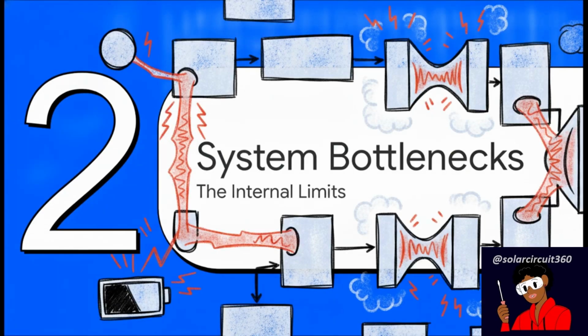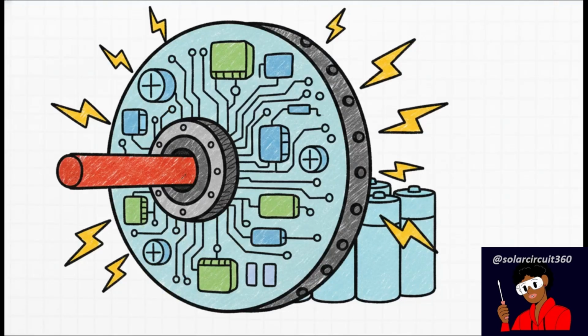Which brings us to system bottlenecks and those strict internal limits. You see, even if your lithium cells are fully charged and ready to go, the internal battery management system, the BMS, usually has a very strict maximum continuous discharge limit. Most standard batteries out there come with a 100 amp, 150 amp, or maybe a 200 amp BMS. So think back to our math a second ago. If your inverter suddenly demands 231 amps, but your single battery only has a 150 amp BMS, it's going to instantly trigger a disconnect to protect the cells. From the outside, it looks like your inverter just randomly died. But actually, it's just the BMS doing its job, protecting itself from that capacity mistake we talked about.